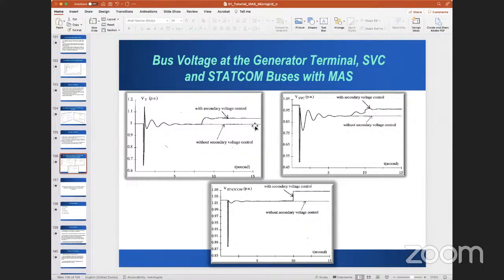AVR is not doing anything because at its terminal it is seeing the voltage within limits, 1 per unit, that's a good voltage. But the SVC is seeing the voltage violated, below 0.95 here. So it's taking help from both controllers.